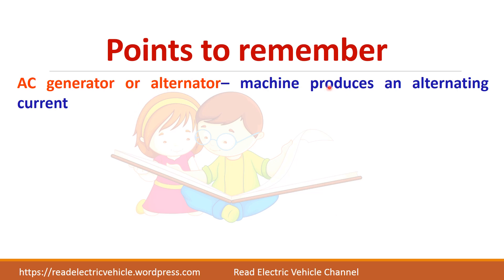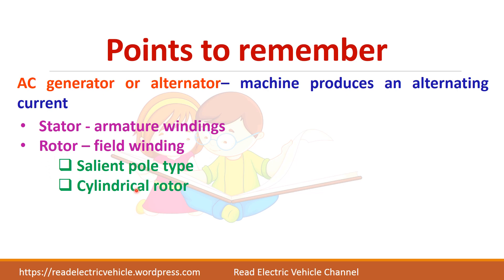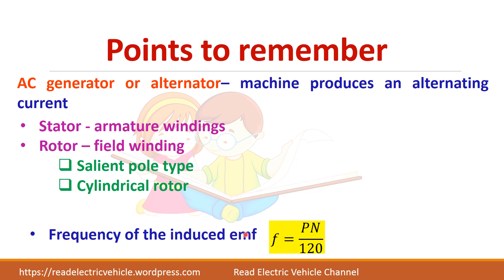To summarize: an AC generator, otherwise called an alternator, is a machine which produces alternating current. In its stator it has the armature winding and in its rotor it has the field winding — just opposite to a DC generator. There are two types of rotor: salient pole rotor and cylindrical rotor. The frequency of the induced EMF is given by F = PN/120, where P is the number of poles and N is the speed in RPM.